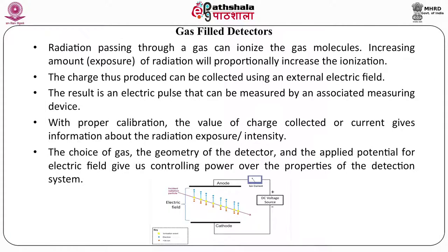For a gas-filled detector, if you fill gas in a container, radiation passing through the gas can ionize the gas molecules. Increasing the amount of radiation will proportionally increase the ionization. The charge produced due to ionization can be collected using an external electric field — for example, with a cylindrical container, you apply a voltage between the outer wall and a central electrode. The charge, depending on its polarity, goes to different electrodes, and the result is an electric pulse measured by an associated measuring device. With proper calibration, the value of charge or current gives information about radiation exposure or intensity.